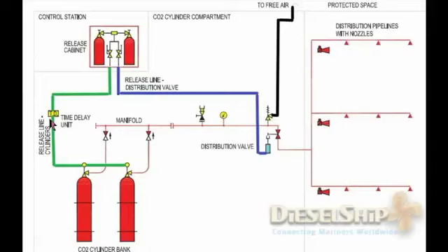The reason why it's kept as an empty bottle is that the CO2 from the pilot bottle takes time to fill up the empty bottle. Thus, this is how the time delay is created. And electronically, we have a solenoid valve and a timer mechanism, which after, let's say, 20 seconds time delay, opens the solenoid, and thus the CO2 goes and opens the main cylinder unit.